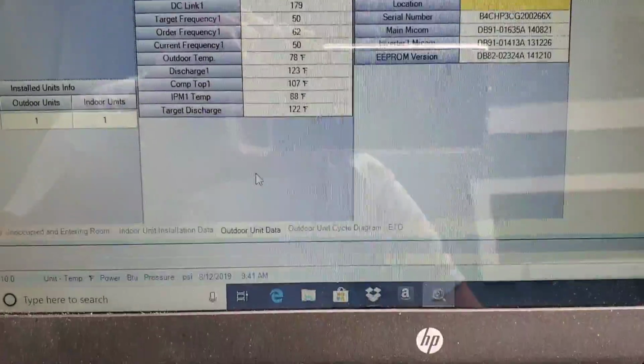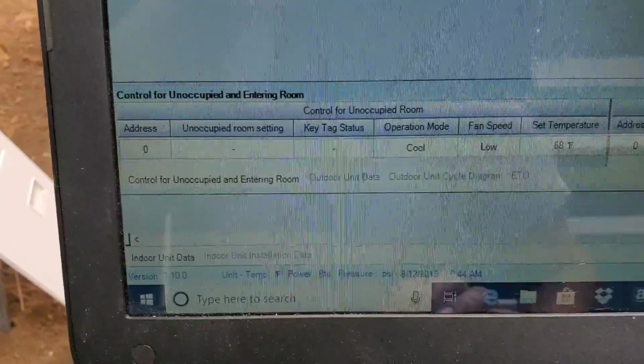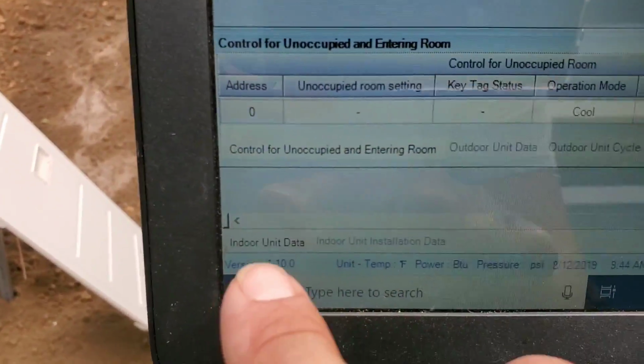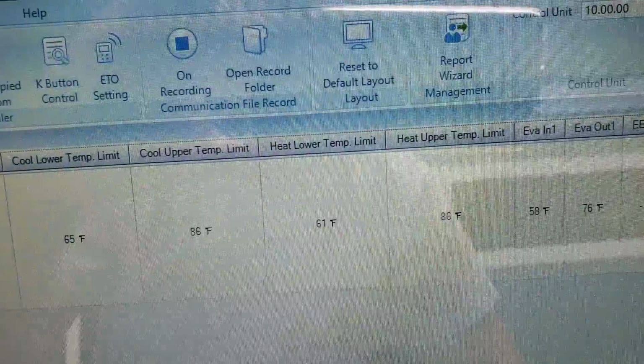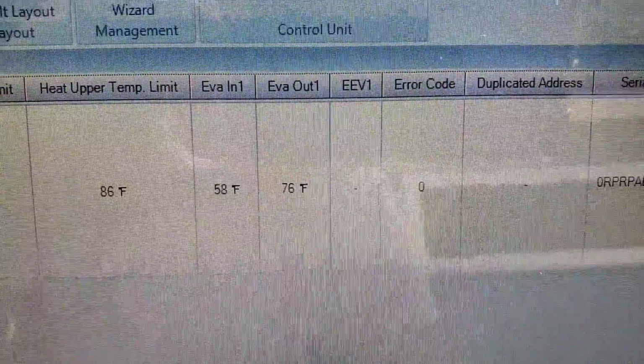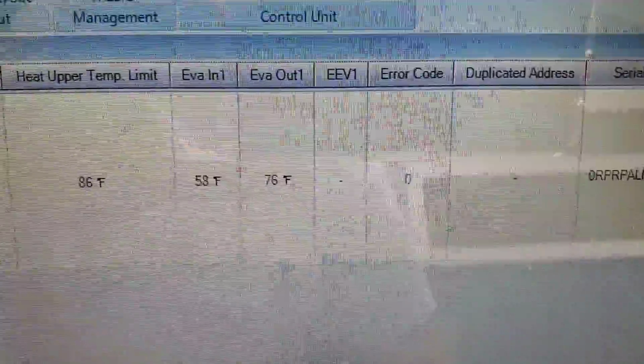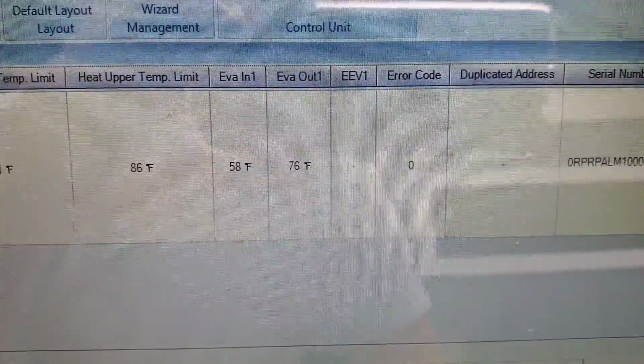Now I'm going to show you guys something pretty cool here. We looked at the outdoor unit data, let's look at the indoor unit data and then the indoor unit installation data. So I go to the indoor unit data and I'm able to automatically see my evaporator inlet is 58, my evaporator outlet is 76. Now you want a really close temperature difference. Right now we know something's wrong with this unit, so I definitely need to check out the charge.